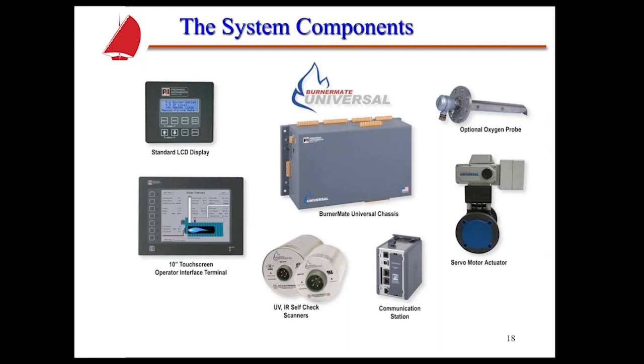You have to have the chassis, as I said before, so the actual brains of the system has to be selected. And again, it depends on how much control you want to incorporate. If you wanted to do, for instance, like I said before, a fully metered cross-limited type system and parallel positioning, then you'd want to select a system like the BurnerMate Universal. We've got to select a UV or IR or self-check scanner. We've got to select a flame scanner. We have to select our servos. We're going to have a servo for each one of those valves that we're going to control. And if we want O2 trim, we're going to need to select an O2 Probe.